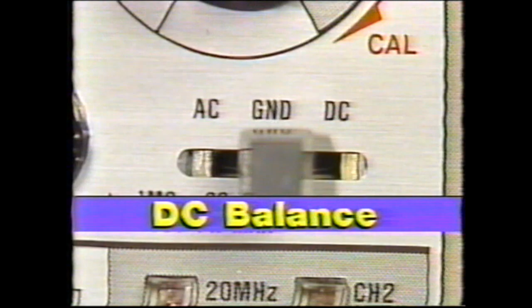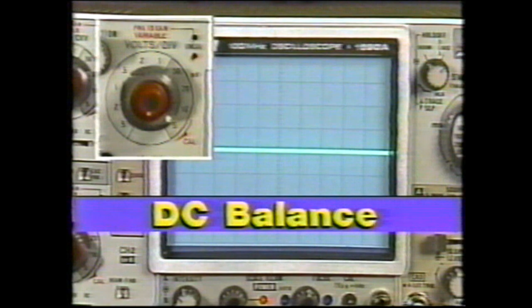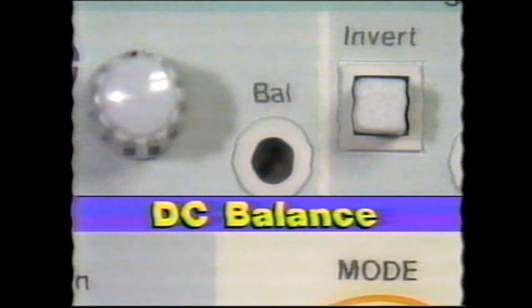To adjust the DC balance, place the AC ground DC switch in the ground position. Rotate the channel 1 volt per division control through all positions. The trace on the display should not move vertically. If there is any movement between adjacent attenuator settings, compensate by adjusting the DC balance control. Repeat for additional channels. In addition, check the calibration of the oscilloscope and probes.